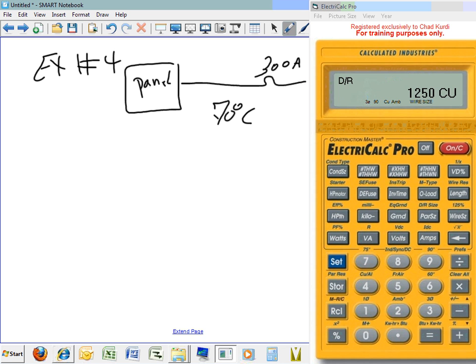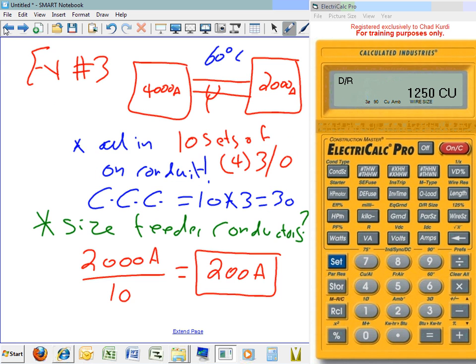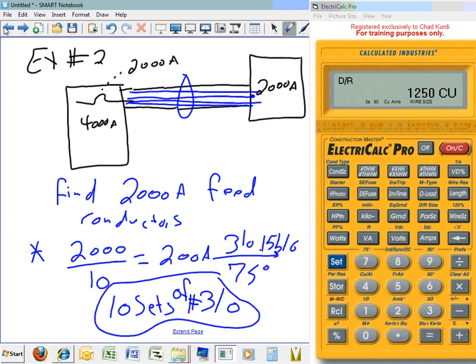We already did the calculation based on continuous. Remember, we came up with 3-aught based on continuous. Right? Oh, wait. Let me go back here. Oh, when I didn't multiply this by 1.25. Yeah. Good point. Because when you go between panels, guys, the 1.25 factor is already incorporated in the load. When I decided I need a 2000 amp panel, I already did all my load, multiplied the continuous load by 1.25 plus the non-continuous load, added them all up, and made up my mind that I need a 2000 amp panel. So the 1.25 factor, especially panel to panel, is already incorporated in there.